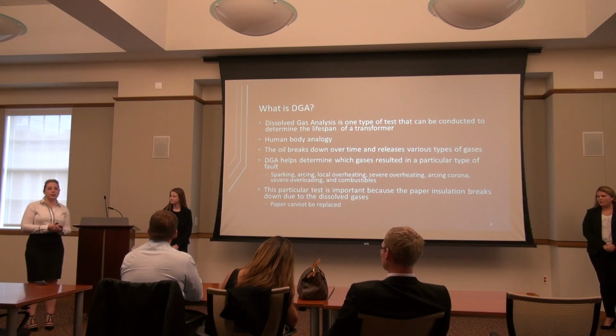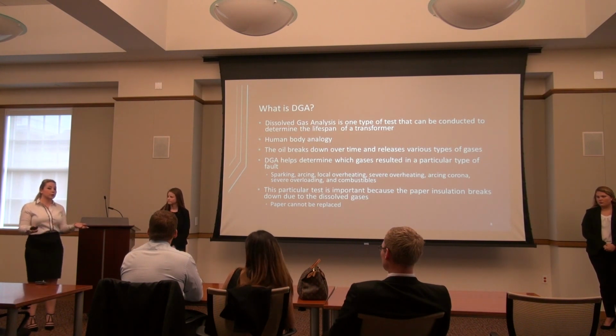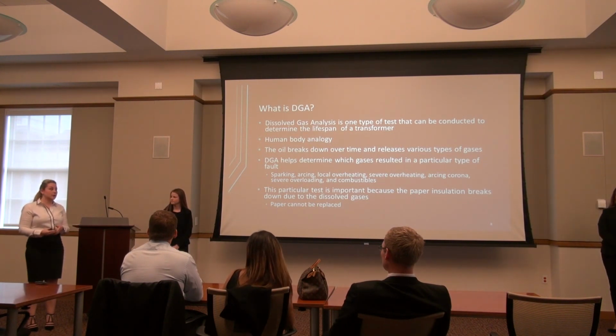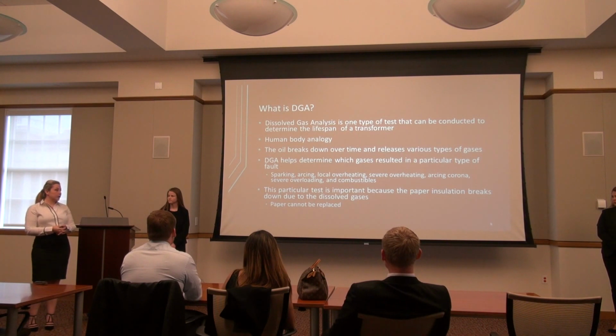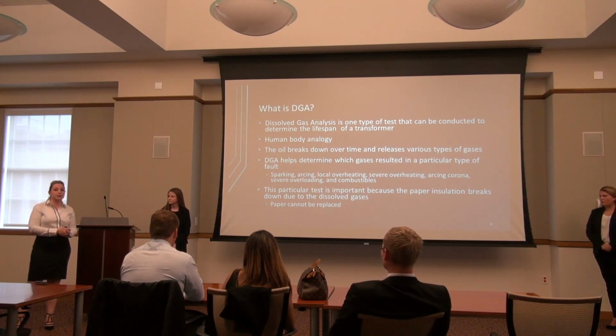This is really important because transformers cost millions of dollars, and it also takes about a year for a transformer to be replaced. So if a transformer were to blow up, it's not a cheap fix and it's not a quick fix. Also, looking at that one particular substation, if one of their transformers were to blow up, they're down half their ability to distribute electricity, and that can be a serious problem for the company. Another reason why this test is so important is that the gases can break down the paper insulation, and this can seriously impact the way the transformer breaks down, and once the paper is gone, it's gone for good. There's no replacing it. So this is a major issue, and it's one of the reasons why we take a look at the DGA, to keep track of the faults that are occurring and to make sure that the transformer is staying as healthy as possible for as long as possible.